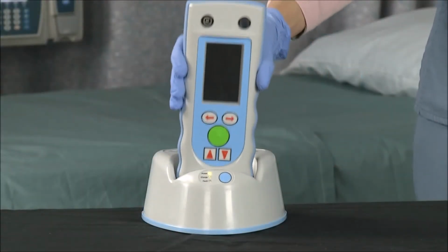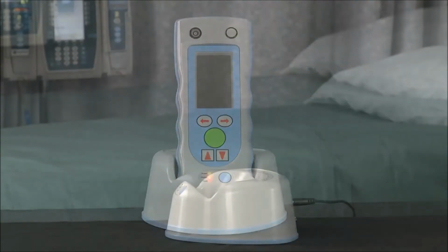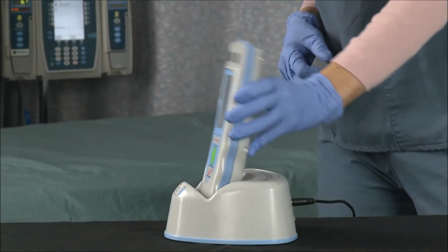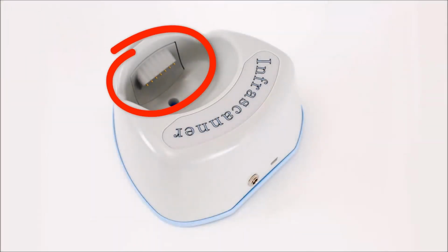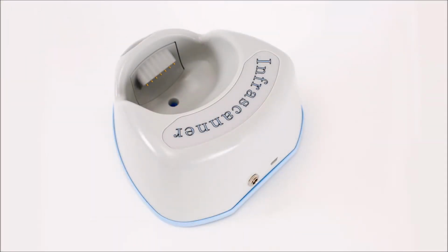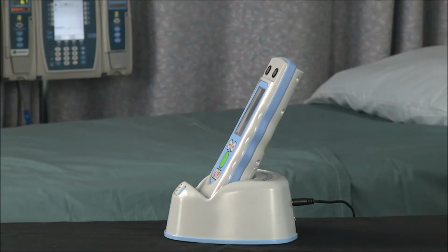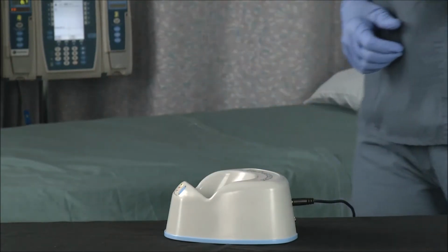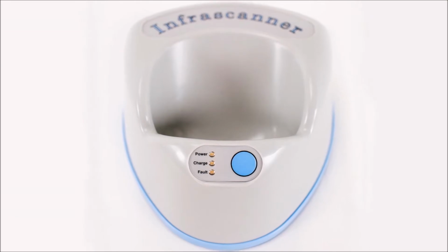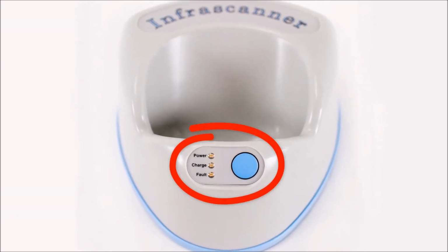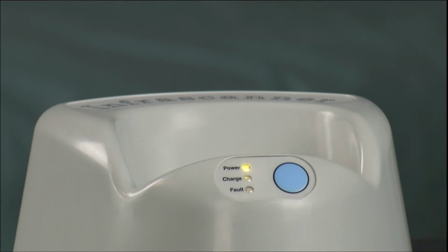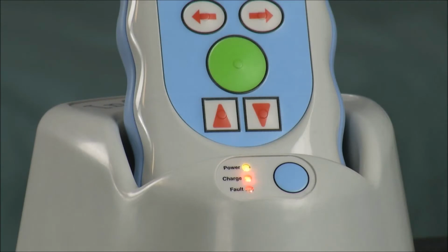Place the Infrascanner in the cradle to charge the unit. Insert the Infrascanner vertically and then lean it backward, making sure to engage the spring-loaded cradle pins. To remove the Infrascanner from the cradle, simply tilt the unit forward and lift. To determine if the Infrascanner is charging properly, simply take notice of the cradle. When the green light is on, it means the charging cradle is plugged in and powered on. When the Infrascanner is in the cradle and the amber light is on, the unit is charging. When the amber light goes out, the unit is fully charged.